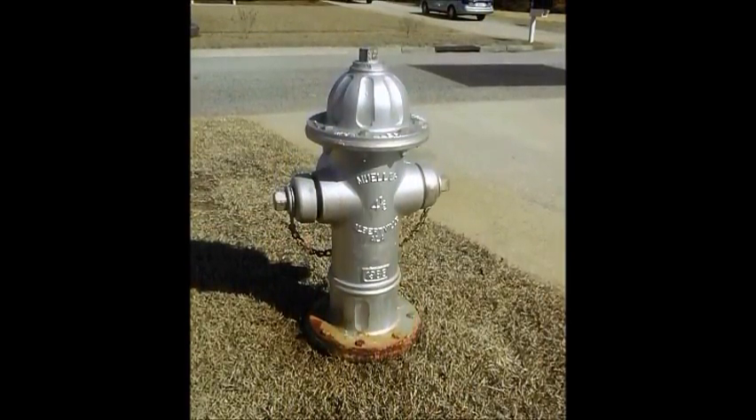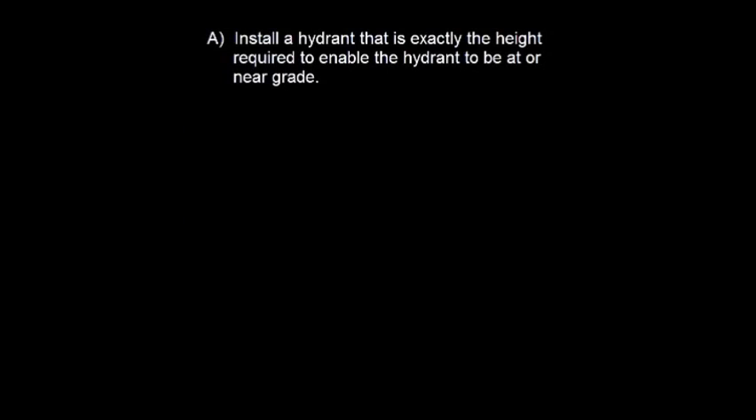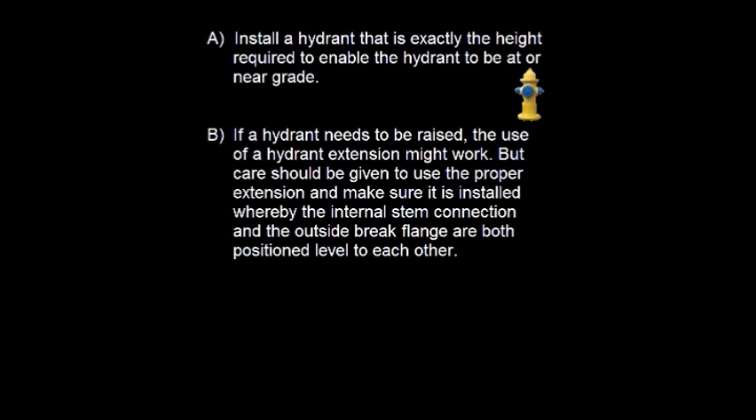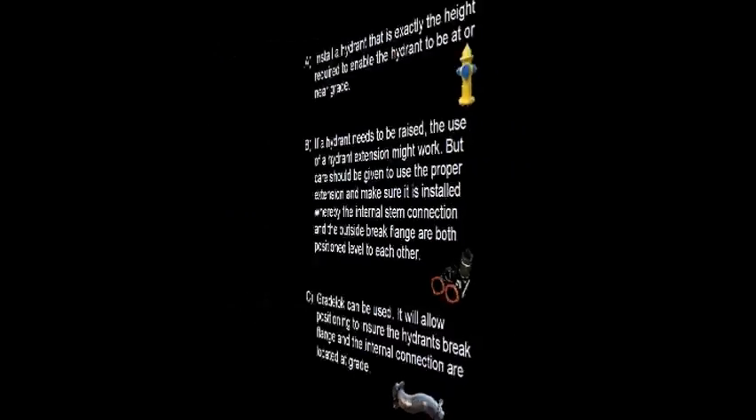There are several solutions that enable a hydrant to be installed at grade. A: Install a hydrant that is exactly the height required to enable it to be at or near grade. B: If a hydrant needs to be raised, the use of a hydrant extension might work, but care should be given to use the proper extension and ensure the internal stem connection and the outside break flange are both positioned level to each other. Or C: Grade Lock can be used — it will allow positioning to ensure the hydrant's break flange and the internal connection are located at grade.